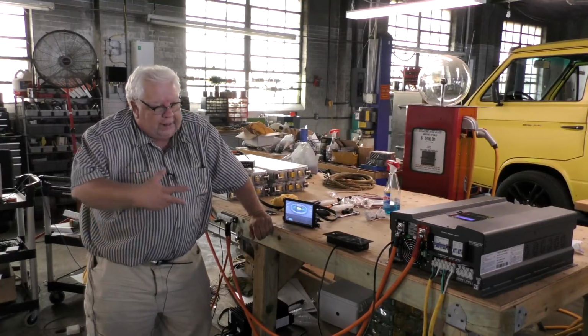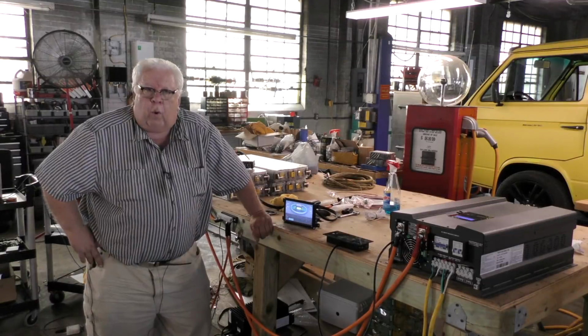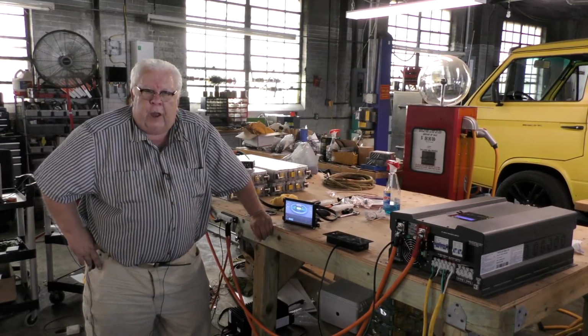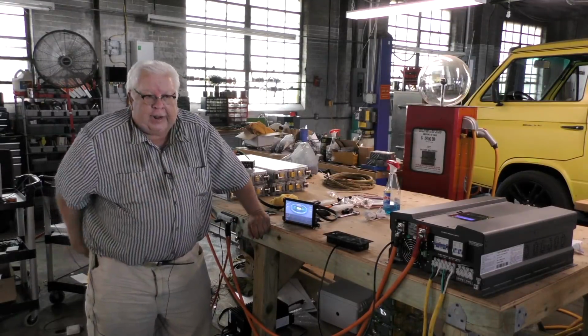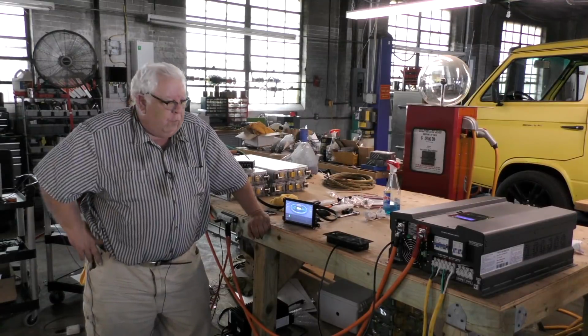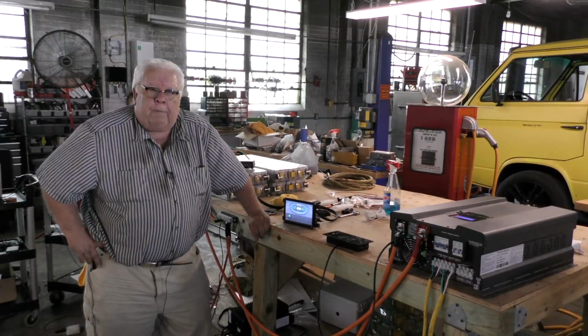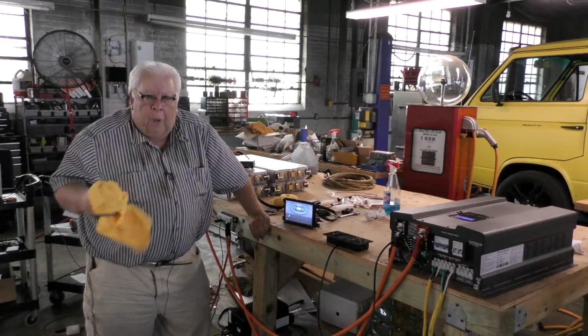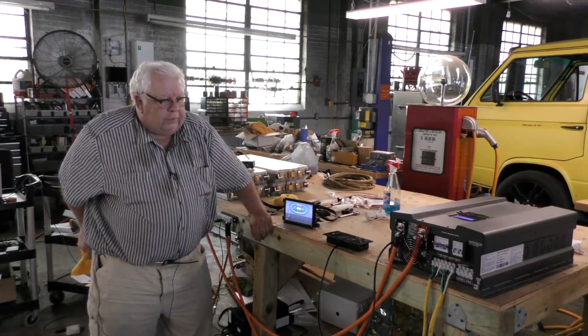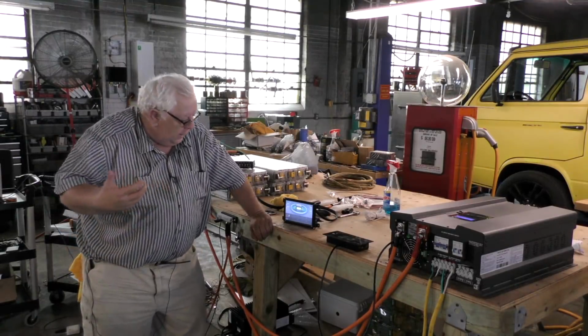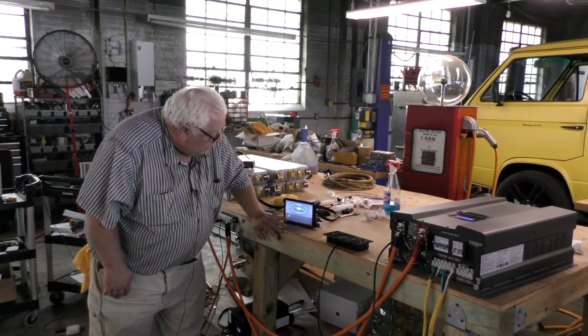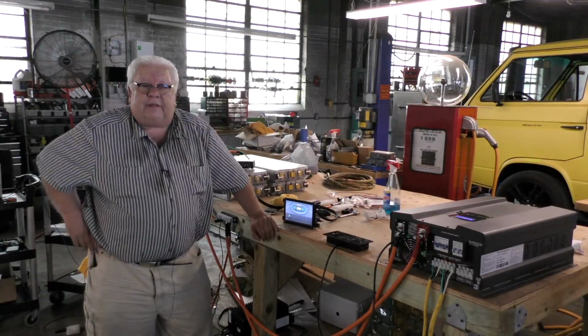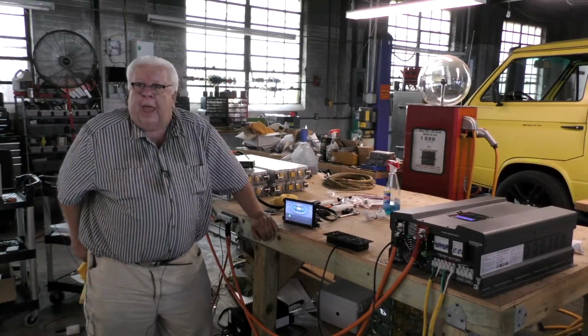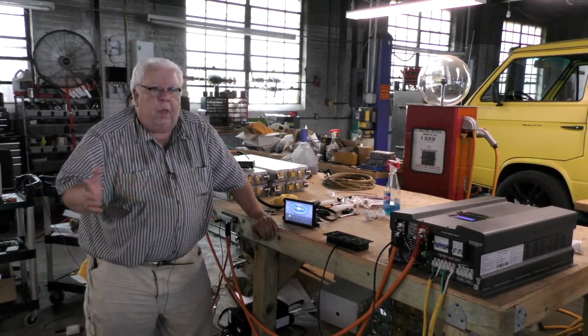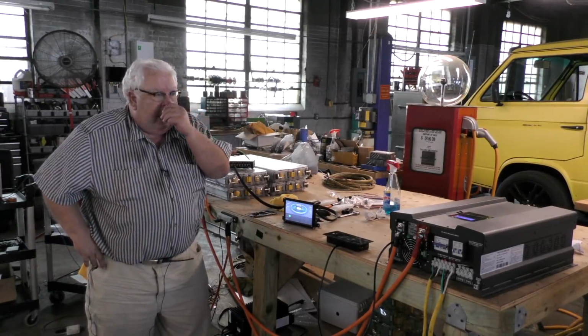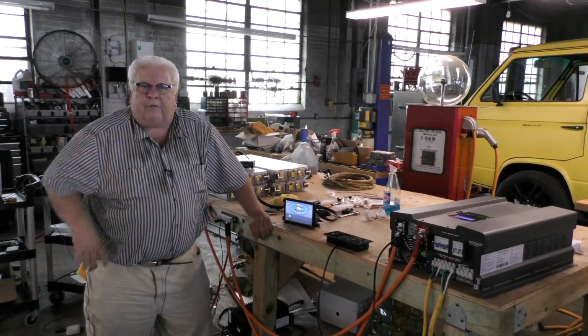But while that's switching in there, we have a 48 volt primary and a 240 volt secondary on a large transformer, and then an H bridge switch that is controlled by the control circuitry. So it's working to invert, but there's more power, a higher voltage on our system, than this is regulating the voltage to in the inverter, and that's forcing energy back into the battery. A little cloud cover comes over, and so we're at 26 amps discharge now in the face of the clouds, and as they dissipate, it'll go back and forth dynamically between charging and discharging as the overcast haze waxes and wanes over our solar panels.